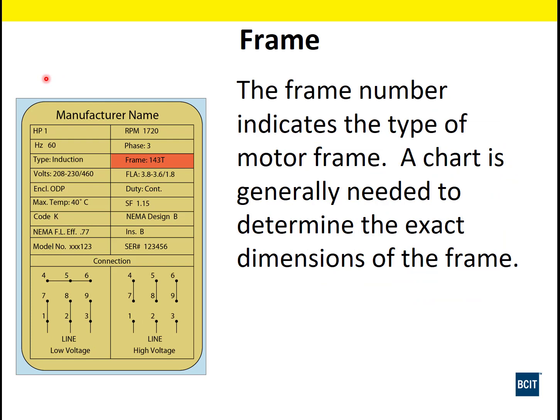Okay, the next one is the frame. Frame number indicates a type of motor frame. Why that's important is this frame number here, let's say 143T, that we can take to a table and it's going to give us all the precise dimensions for the motor: the bolt pattern for the feet, the shaft diameter, the difference between where the motor's sitting flat from the ground to the center of the shaft, the length of the motor and all that. And we're going to have a look at that in a second.